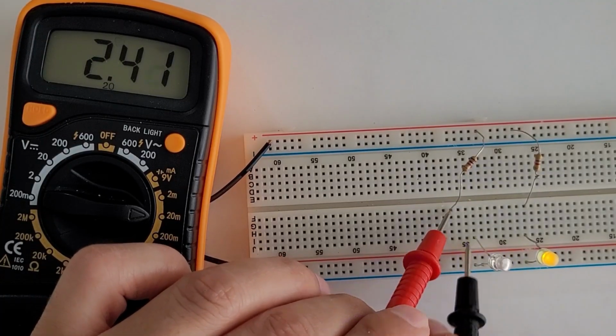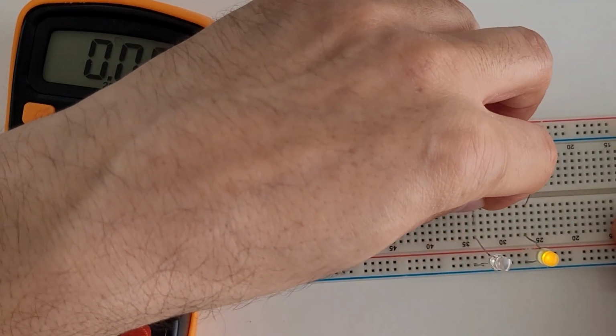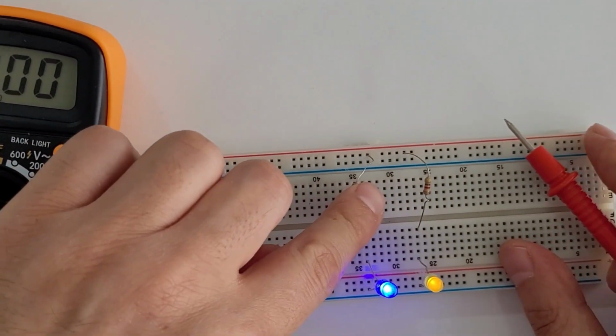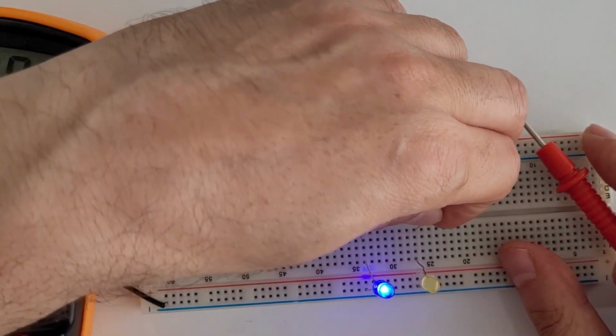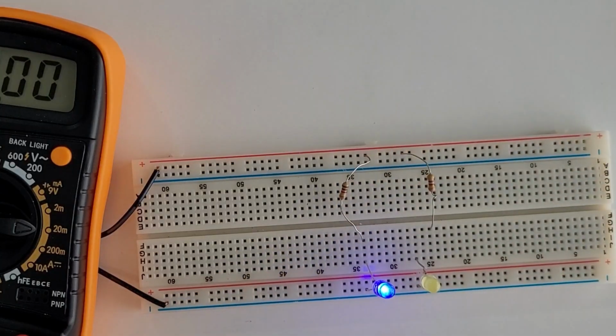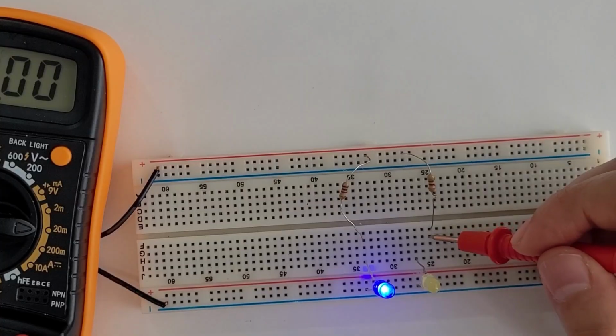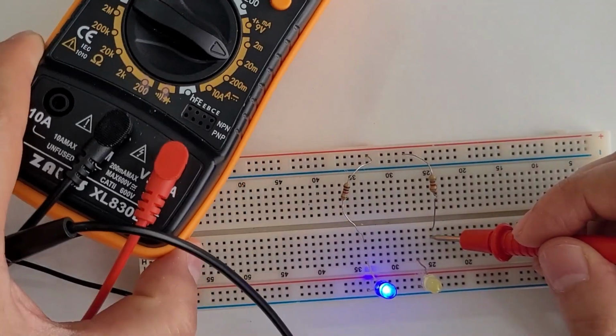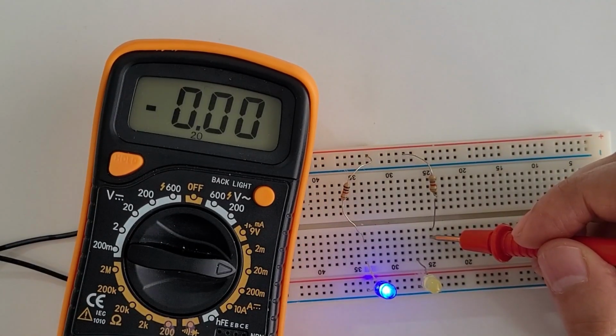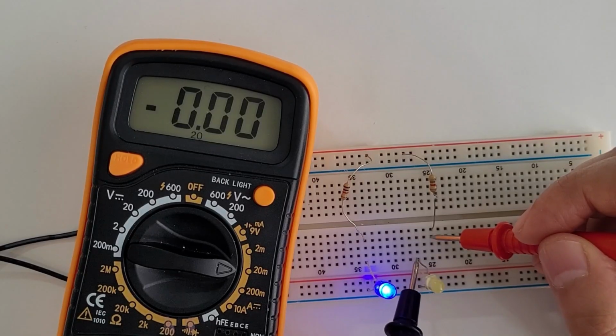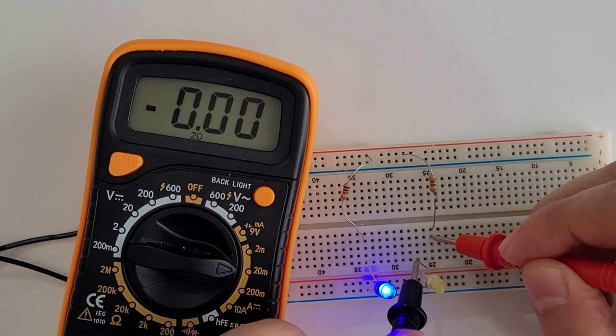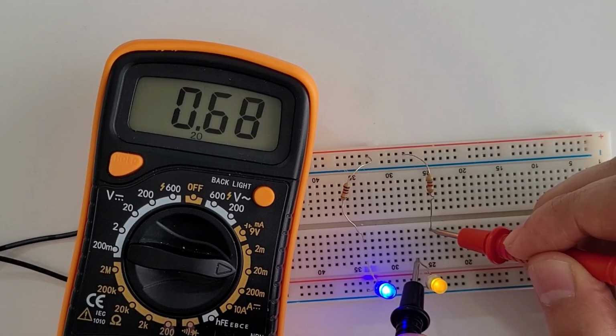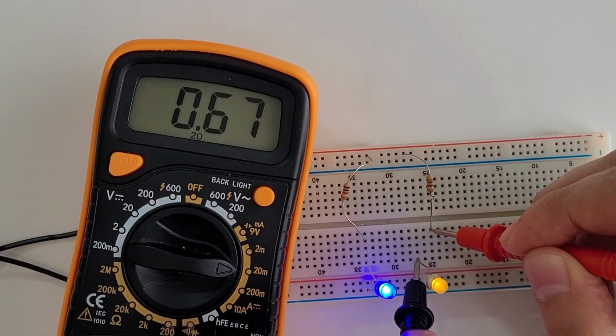The first branch was 2.41 milliamperes. Let's power up our circuit again and now measure the second branch. We'll isolate the second branch the same way and disconnect this one too. Let's check the second branch using the probes like this. Our second branch is drawing about 0.68, or 0.67.